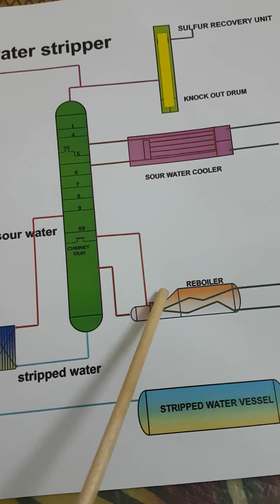But in the reboiler we only use medium pressure steam. Other companies, in most units, use thermic fluid to heat the sour water, but as per the design or temperature requirement, we use steam here. So this is the reboiler, and these are the coils in which steam comes in and goes out. So the sour water temperature will rise, and from here sour water gets heated. This is the function of the reboiler.